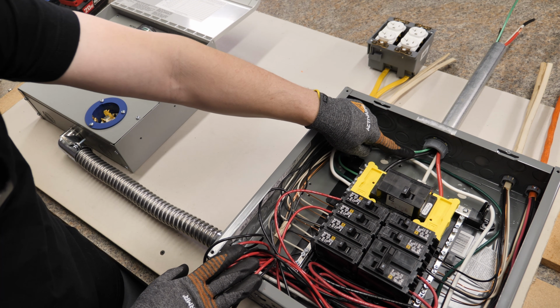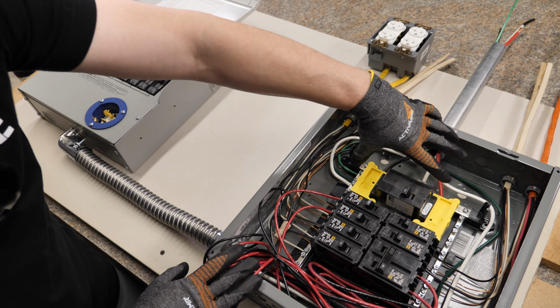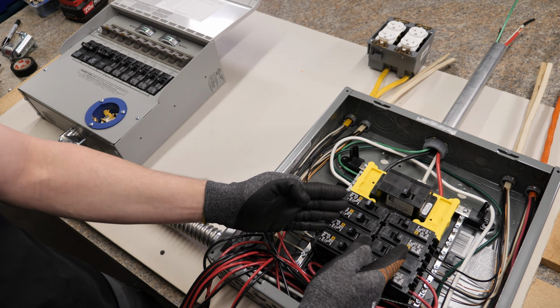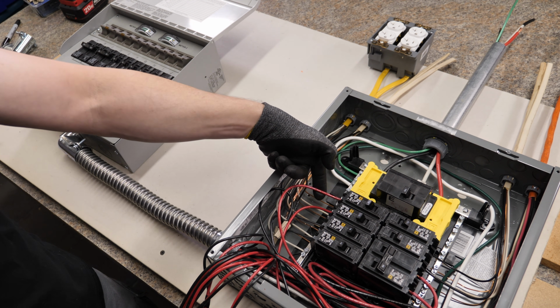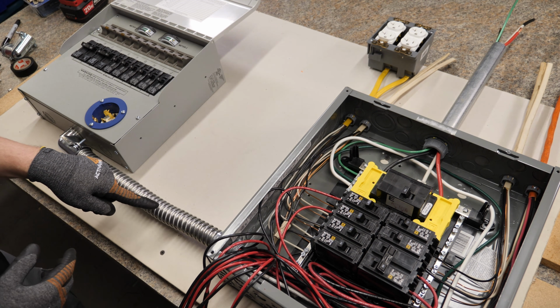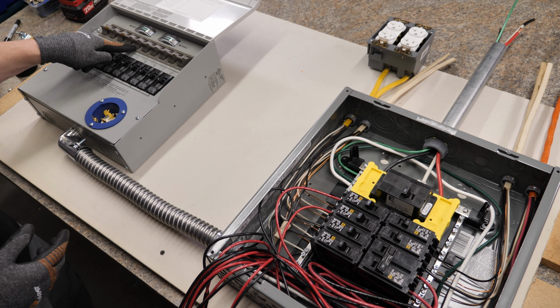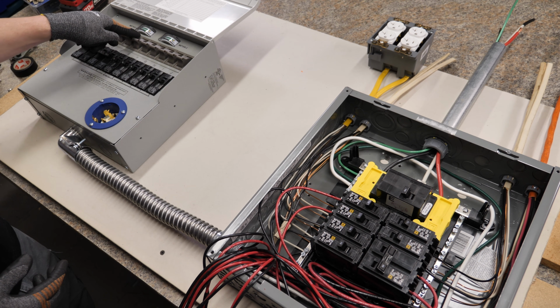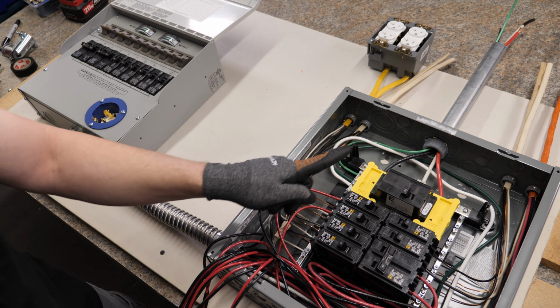Starting over here, these wires up here come in through the grid, go down the side bus bars, which come out through the circuit breaker, go out the red wire, which go over here through the conduit, and since we are in the grid or line mode right up here, basically it just circles back out to the load as it normally would.